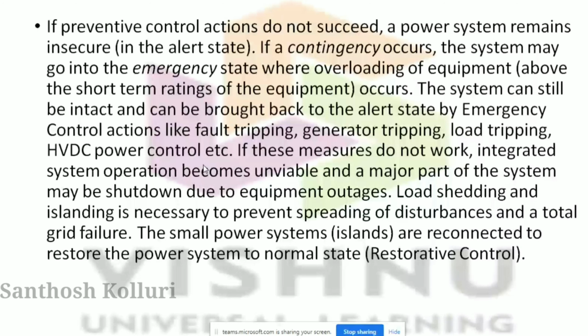A very simple concept here. When there is a fault, you should take certain preventive actions in the alert state. If the contingency occurs again continuously, that may lead to an emergency state where there is overloading of the equipment or overloading of the generators. Still, if you do not take any action on it, then the grid may collapse. So in that case, in an emergency state, you have to take certain actions to bring it from the emergency state to the alert state. The general things you do for that are shedding or switching of plants, shutdown of plants, tripping of the load or disconnecting the load, or HVDC power control. All these are measures which bring the emergency state back to the normal alert state.